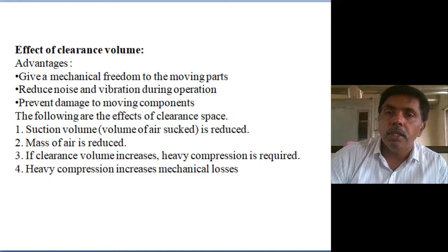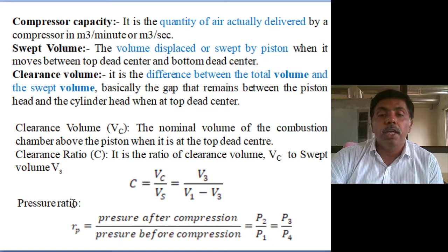Compressor capacity means the volumetric flow rate, meter cube per second. Swept volume, as mentioned, is the piston movement volume, pi by 4 d square into L, between the two dead centers, bottom and top dead center. Clearance volume is the total volume minus the swept volume. Then clearance ratio is clearance volume to swept volume, that is V3 over V1 minus V3. Pressure ratio is pressure after compression by pressure before compression. Volumetric efficiency is the effective swept volume by the theoretical swept volume.